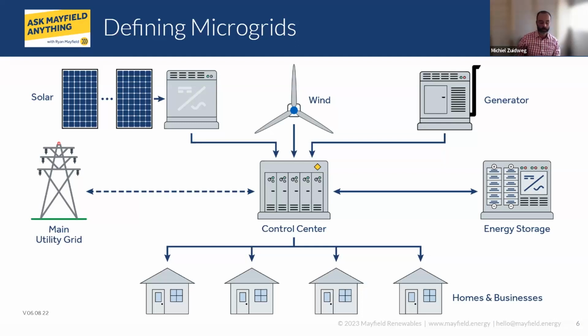Another example is a local utility here in Washington. They did a microgrid specifically to divert upgrading a substation and underwater cables between substations and the San Juans. If they didn't reduce that peak demand, then with all the growth in that area, they're going to have to spend a lot of money to replace those cables. But with this microgrid, they were able to defer that for 20 years. So, a lot of financial benefit as well, besides just resiliency.